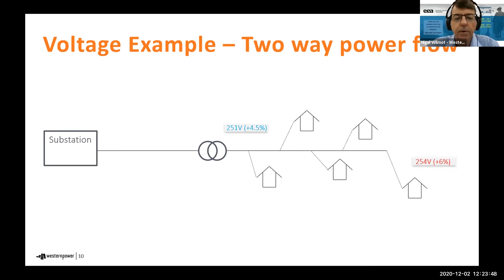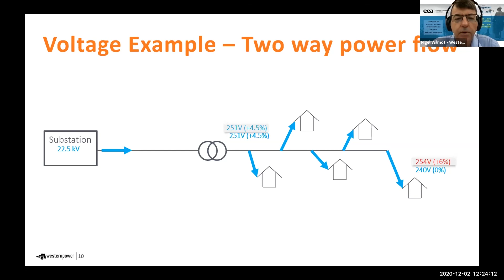And so there's quite a large swing from one end to the other range, and that's very good. A network's good for it. It can handle the two-way power flow. It's just the way we have traditionally set our voltages up at the higher end, and that is what all utilities and DNSPs around Australia and internationally do.